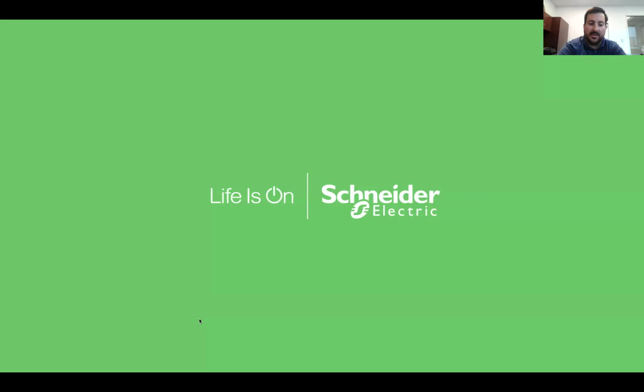If it ran down battery power to the point that the batteries were at a low charge state and you were getting the low battery alarm, basically, it would then kick on the generator, and the facility would run on the generator while the generator was also simultaneously charging the batteries. And then whenever the batteries were fully charged, the generator would shut off again and run on batteries until either utility came back or the batteries needed charge again and go through the same cycle again. So the short version is yes, definitely. We've seen it, we've done it, and I think it's going to be a common use case out there.